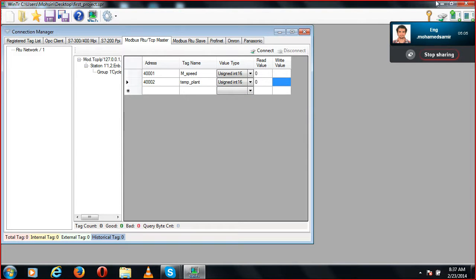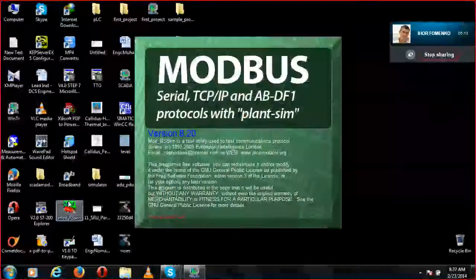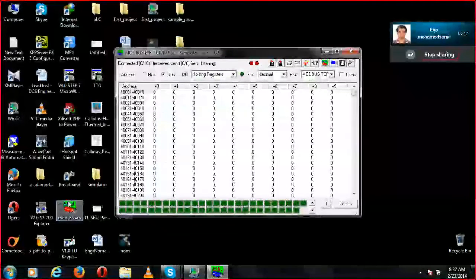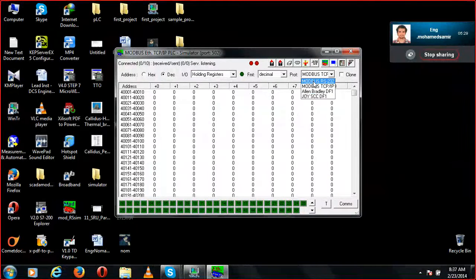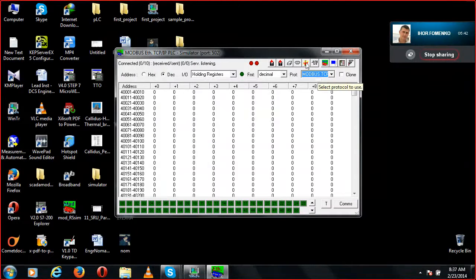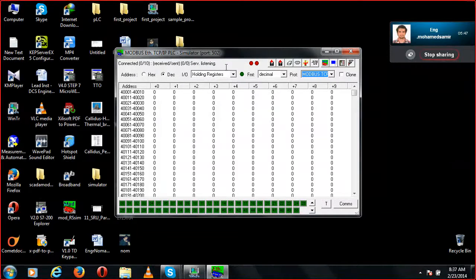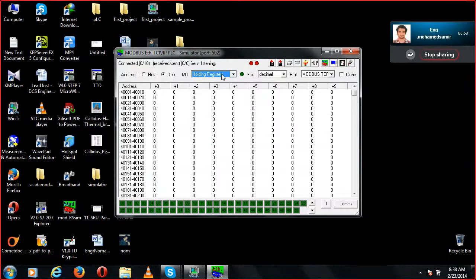The next step is to use the simulator in the backend. There is a Modbus simulator — I'm going to click it and open it. There are a couple of options: RS-232, Modbus TCP. Today we are going to use Modbus TCP. I'm also using holding registers — there are other options like digital inputs, coils, and analog inputs, but today I'm using analog holding registers. That's the address I will be using.